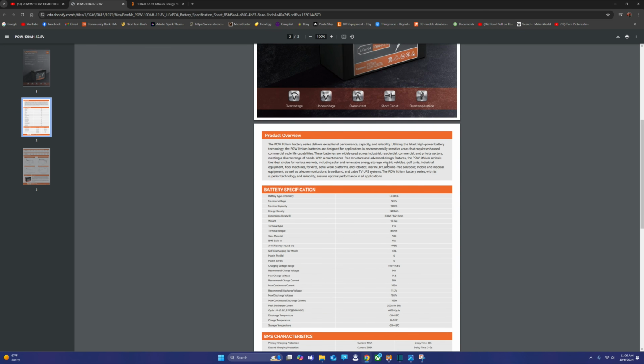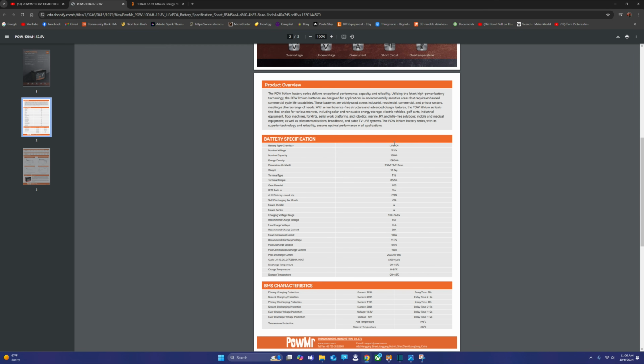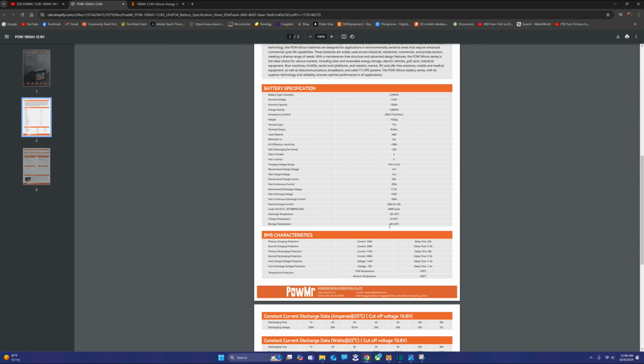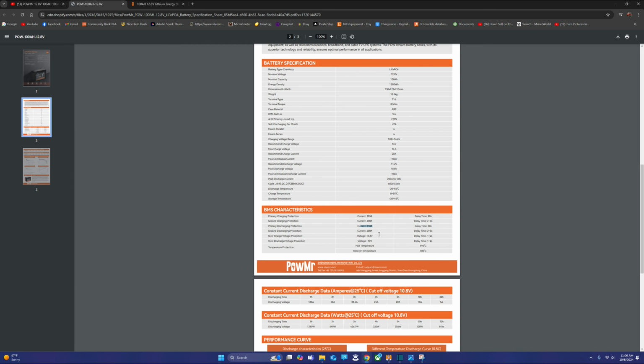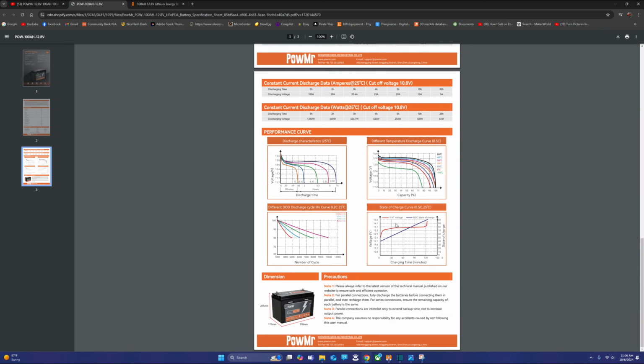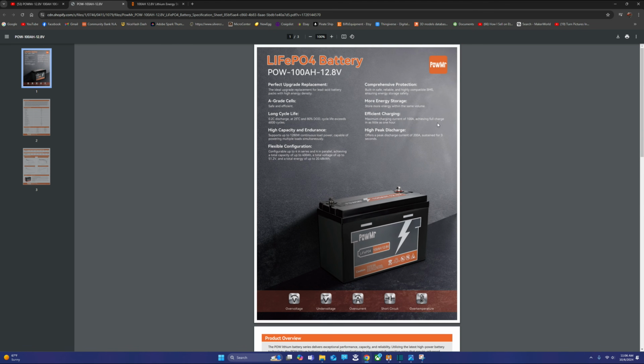On this data sheet, you could find all the specs you're going to need to set up your battery with your inverter. It tells you the voltage, the series, the watt hours, the amp hours, basically all the specs you need, the current, what the maximum allowed current is, what the lowest voltage should be, the highest voltage should be. So this is really important to have this data sheet.